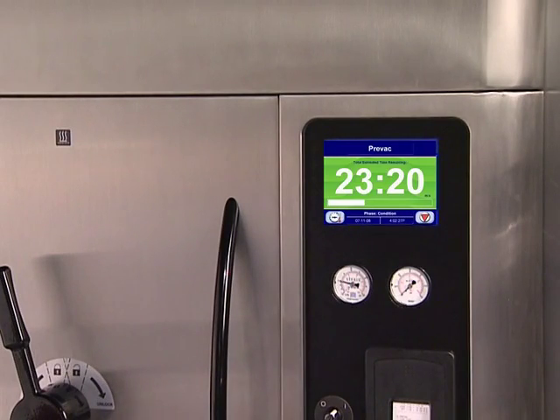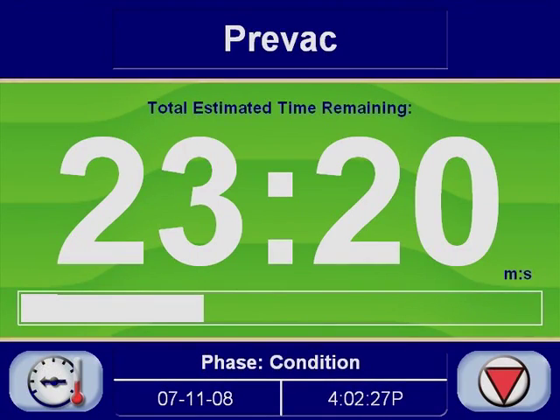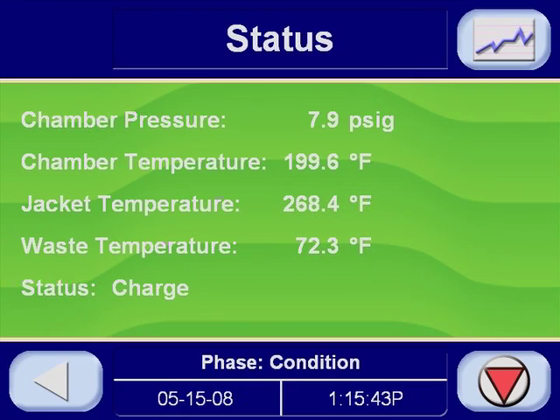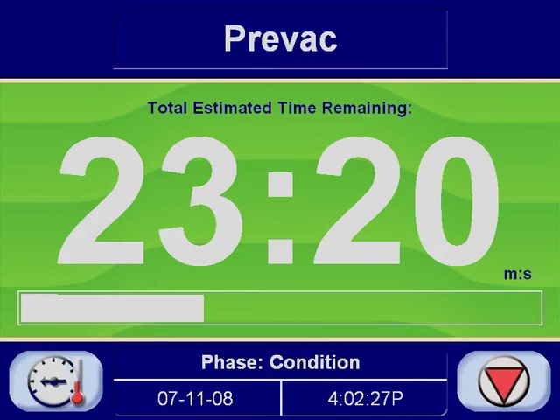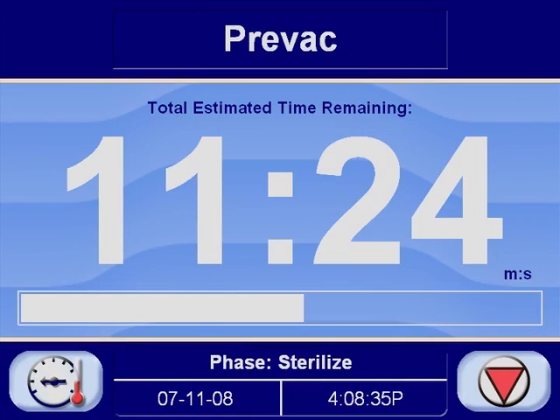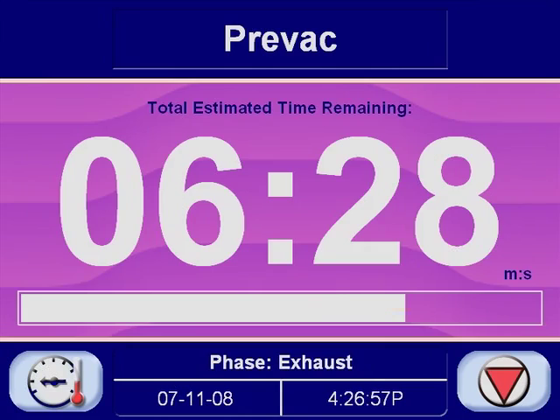A time-remaining countdown is visible from across the room. The large screen displays critical information such as cycle status. You can get more detailed cycle information at any time by pressing the status button on the main screen of the control panel. You can also view a graphical representation of the cycle by pressing the button in the upper right-hand corner. Press the Exit Screen button to return to the main cycle screen. The control panel displays a different background color for each phase in the cycle: green during preconditioning, blue during sterilization, and violet during the exhaust and dry phase.